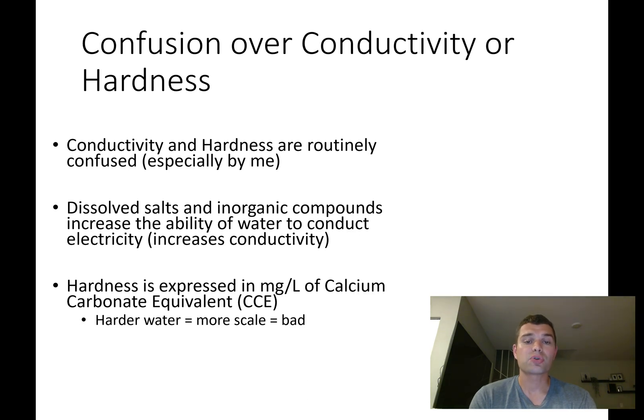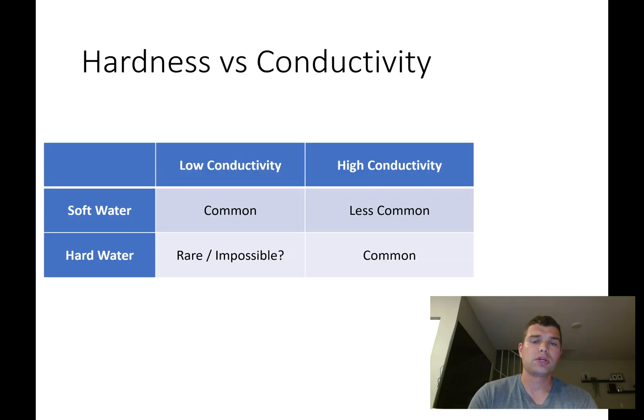Harder water equals more scale, which is primarily calcium carbonate in your cooling water system — and that's not good. It's possible to have low conductivity soft water, which is very common, and also to have high conductivity hard water.